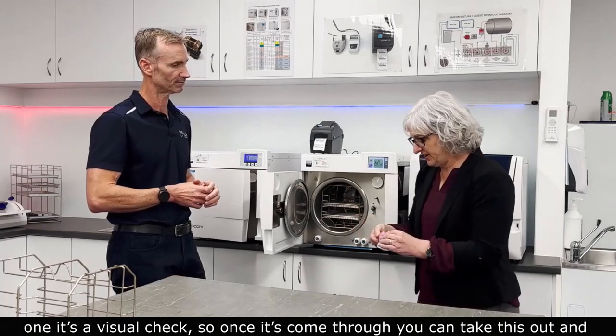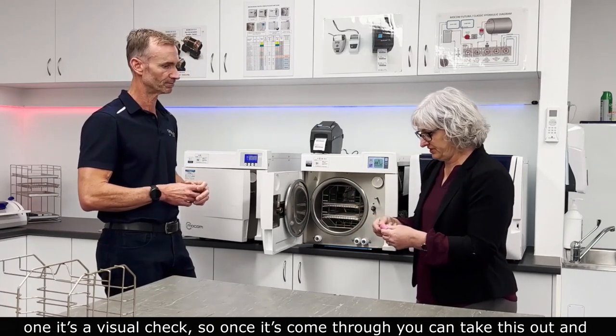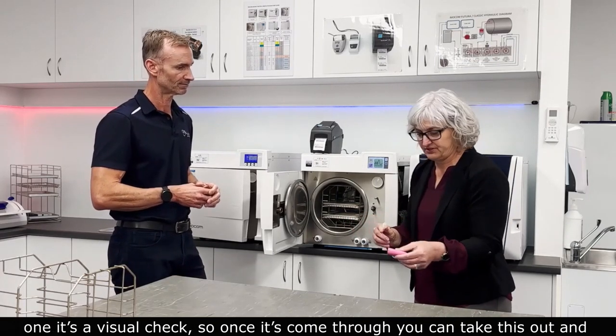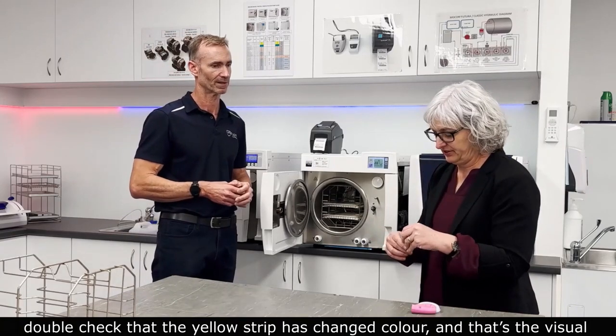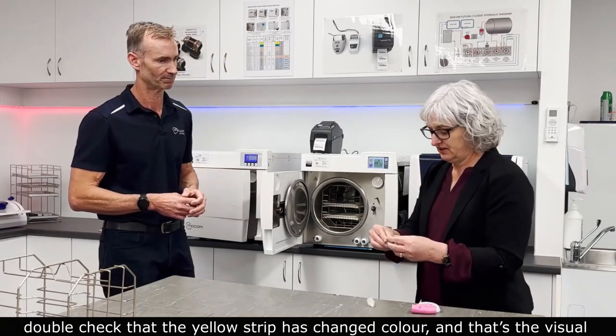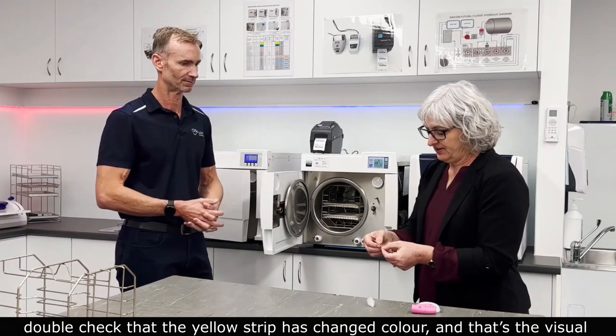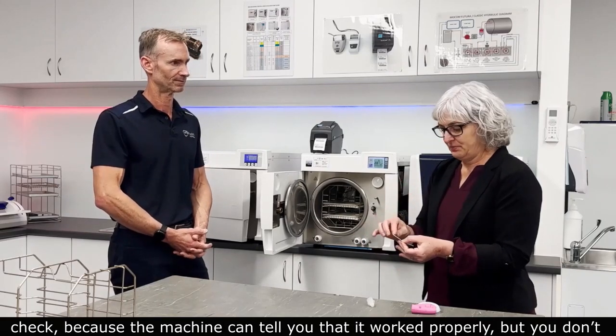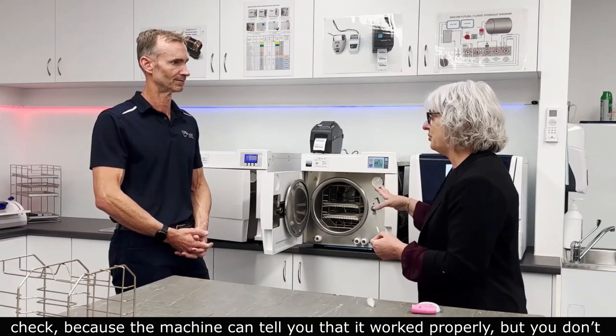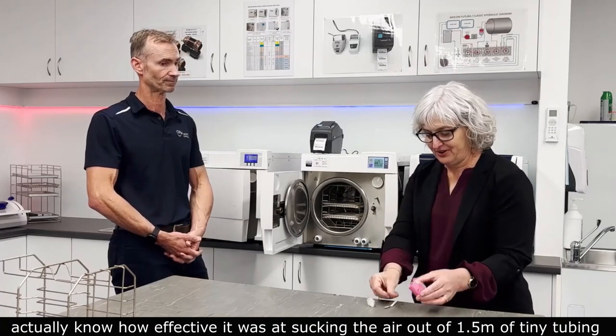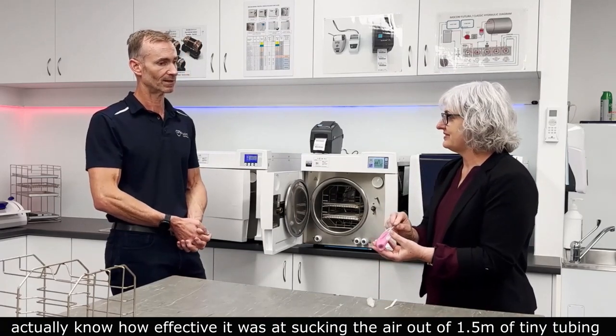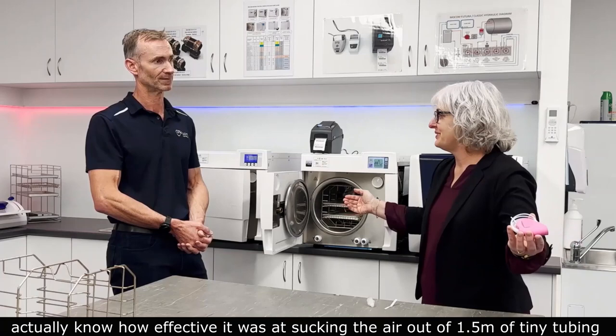With this particular one, it's a visual check. So once it's come through, we can take this out and double check that the yellow strip has changed colour. That's the visual check. Because the machine can tell you that it worked properly, but we don't actually know how effective it was at sucking air out of 1.5 meters.